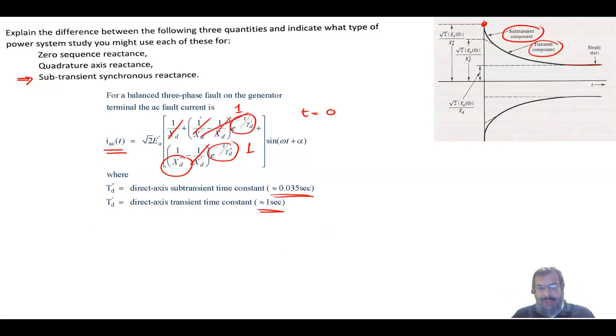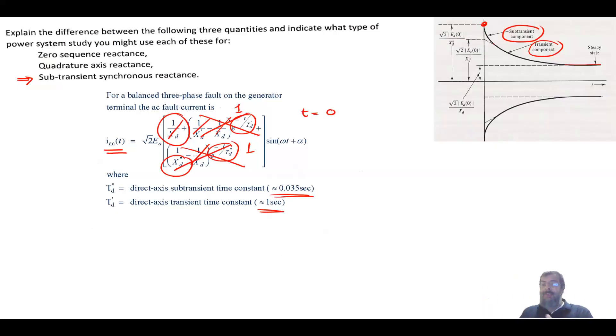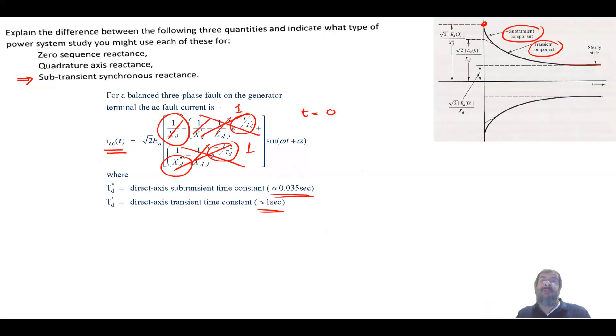As t approaches infinity, the exponential terms go to zero and we are left with one over xd, the synchronous reactance. This is the reactance used under steady state to limit the current — of course, the protection system should have cleared the fault well before that point.